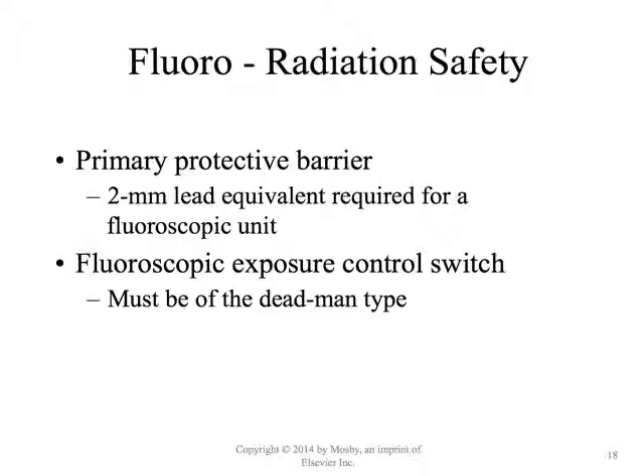So in terms of our personnel protection from scatter radiation, we need at least a 2 millimeter lead equivalent for fluoroscopic units. They operate at a lower kVp than X-ray units, so the 2 millimeter lead equivalent will stop quite a bit of the photons from them, as well as a dead man switch type exposure switch, which means it cuts off if no one's standing on it.